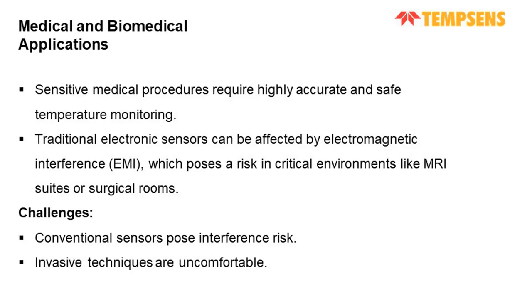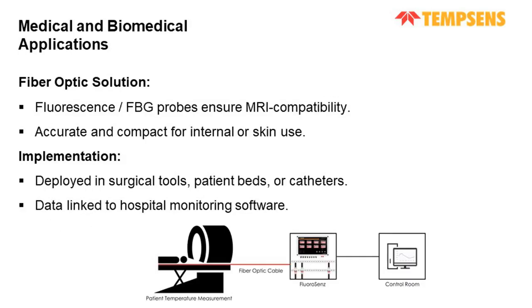So traditional temperature sensors such as thermocouples or RTDs often pose challenges. They can be invasive, bulky, or electrically conductive, leading to signal interference with highly sensitive medical imaging equipment like MRI or CT scanners. Moreover, the use of metal-based sensors in such environments can be dangerous due to the presence of strong magnetic fields. That's where fiber optic sensors can be used, like fluorescence or FBG-based systems, which offer a non-invasive, non-metallic, and biocompatible alternative.